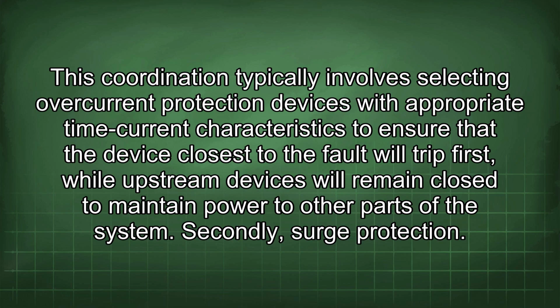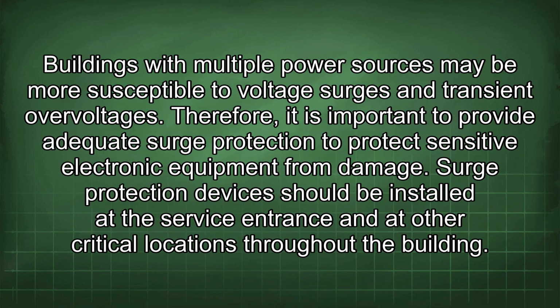This coordination typically involves selecting overcurrent protection devices with appropriate time current characteristics to ensure that the device closest to the fault will trip first, while upstream devices will remain closed to maintain power to other parts of the system. Secondly, surge protection. Buildings with multiple power sources may be more susceptible to voltage surges and transient overvoltages. Therefore, it is important to provide adequate surge protection to protect sensitive electronic equipment from damage. Surge protection devices should be installed at the service entrance and at other critical locations throughout the building.